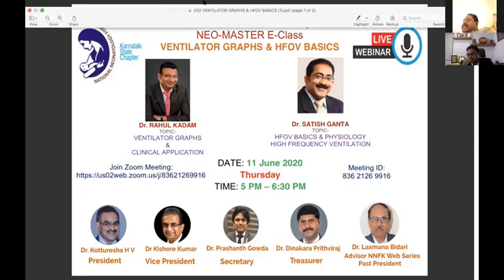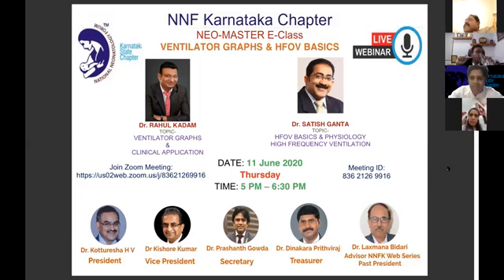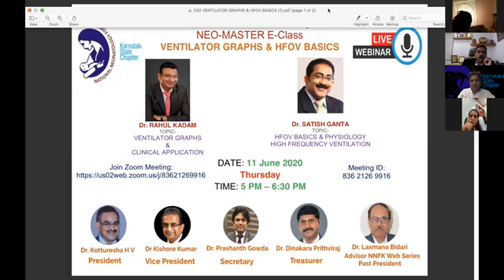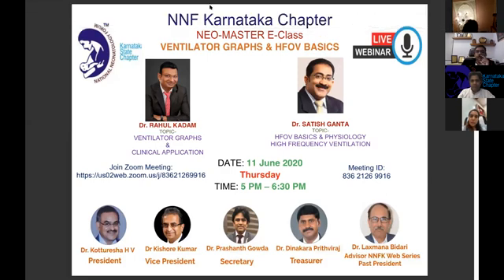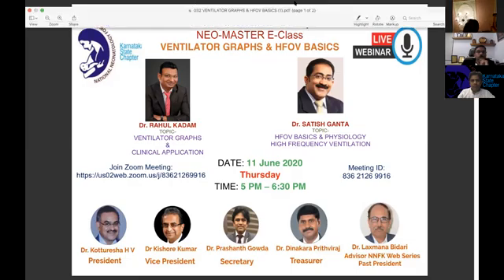Yes. So Doctor, I think you heard the last word he said, which is the main anchor in your question: termination sensitivity. If termination sensitivity were not there, the machine wouldn't synchronize with expiration. Number one, that is called termination sensitivity. Please go to the machine and stand in front of it. What is termination sensitivity? You read the book, whether it is 15%, 25%, 30%, 70%, 80%. Please read it and try to understand. So termination sensitivity is the answer for expiration synchrony. For inspiration synchrony, it is trigger sensitivity.